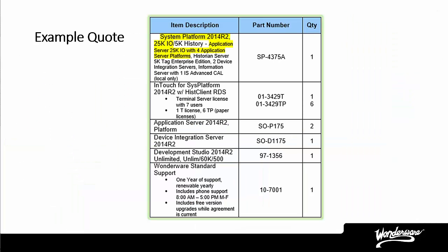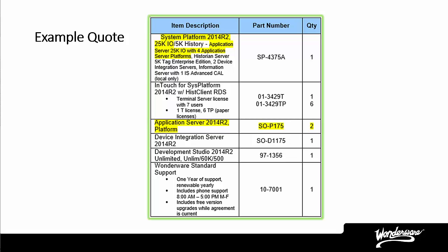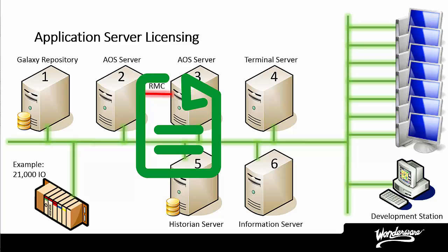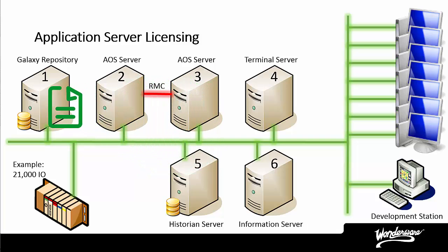If we look at the quote again, you will see that the base Application Server only comes with four platforms. So for our system to be licensed correctly, we need to add two more platforms. That is what the additional highlighted line is for — it adds two more platforms to get us to the required six. The Application Server license is always installed on the Galaxy Repository computer. The Application Server license does not have to be installed on any other computer — this is a common mistake that most customers make.